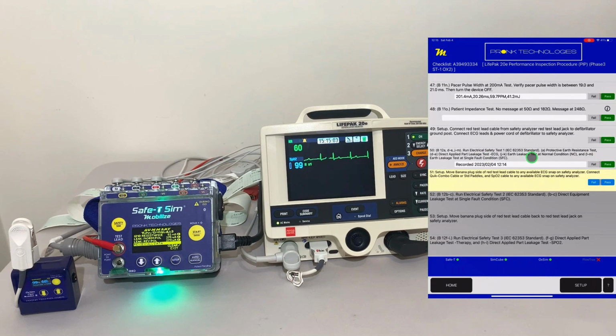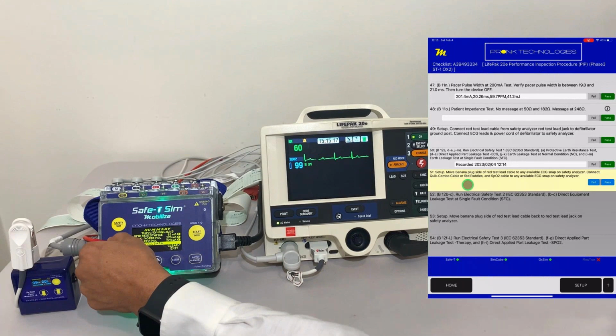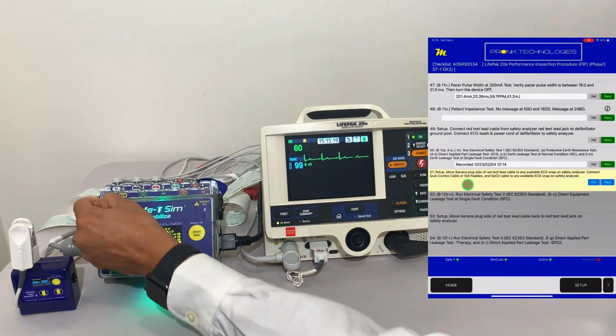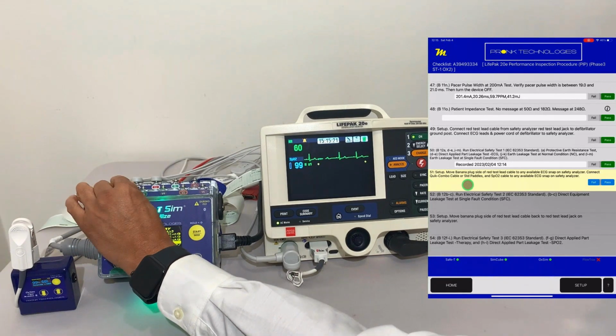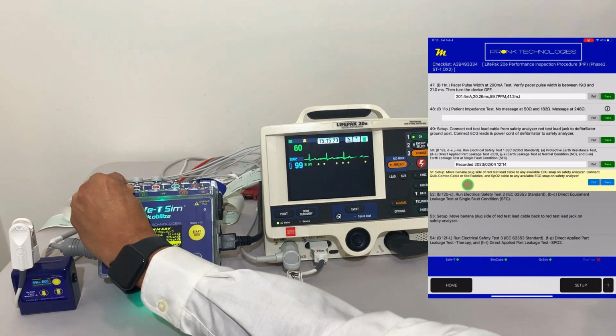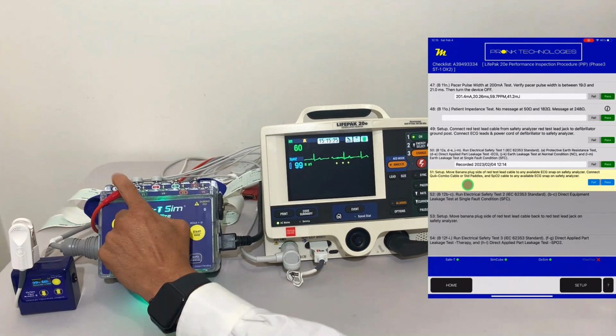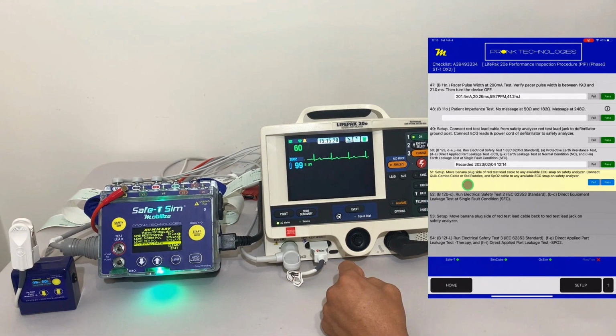Now we need to make sure we go on to the next step. In this particular app, for this defib, there are a series of different electrical safety tests we need to do. So we need to just keep following the instructions. The next step we want to do is move the banana plug side of the red testing cable over to any of the other ECG snaps that are available. So we're going to connect it over here. The analyzer has a banana plug interface, so it allows me to slide that banana plug right underneath that test lead to do that particular test.